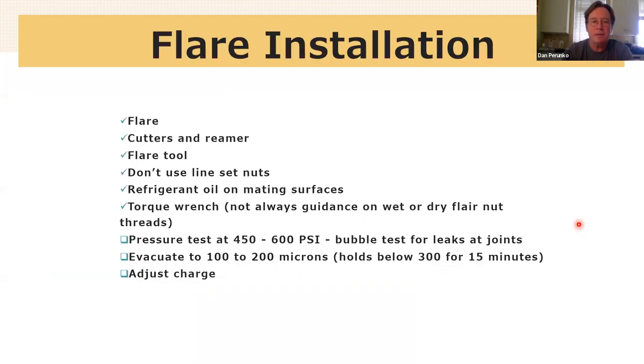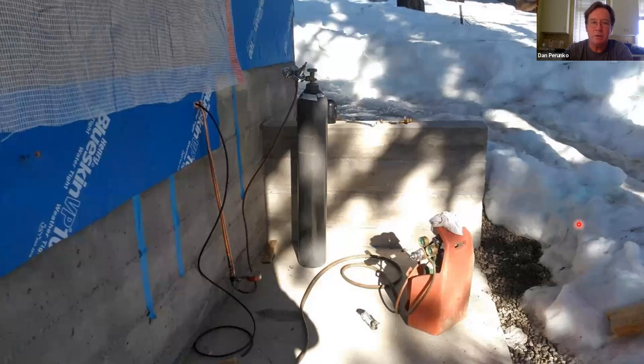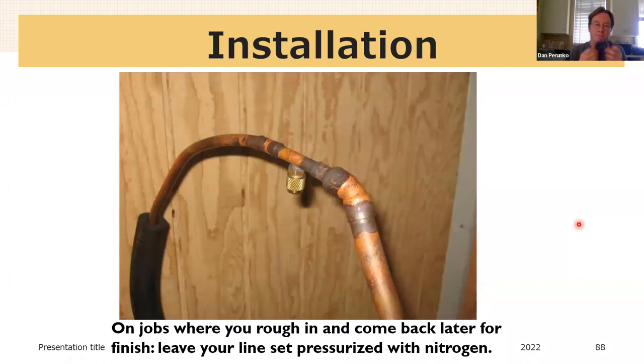And then we get into testing, right? I showed you this picture of using nitrogen pressure to test the system. So we test, depending on the manufacturer, 400 to 600 PSI, 450 to 600 PSI.